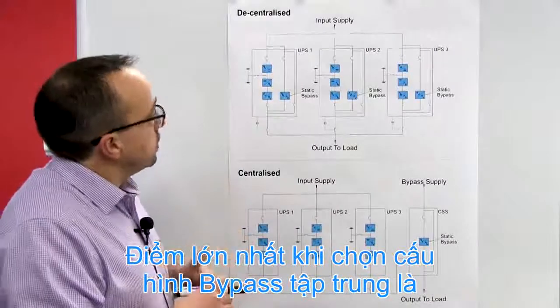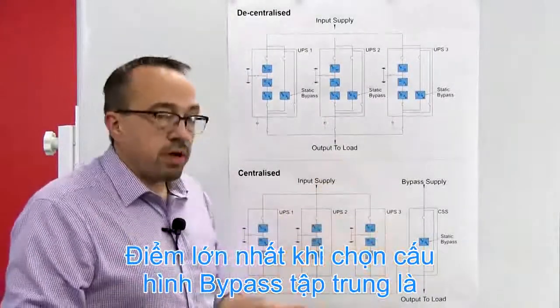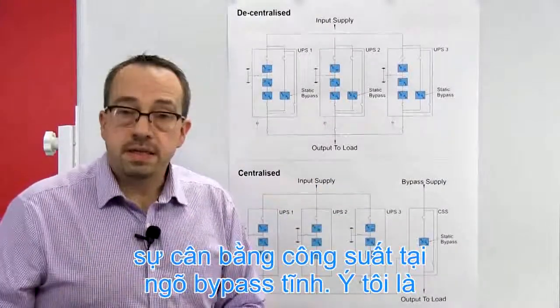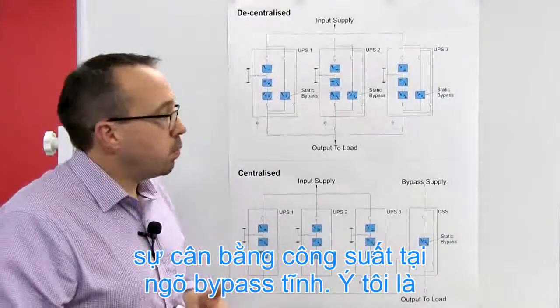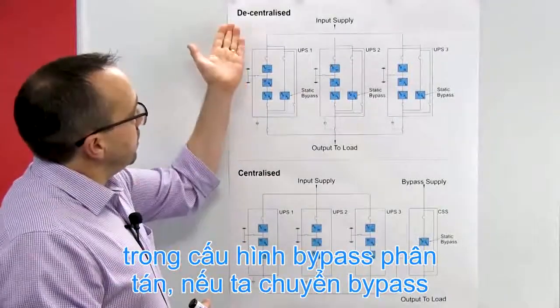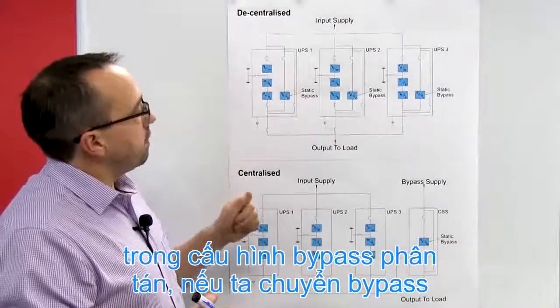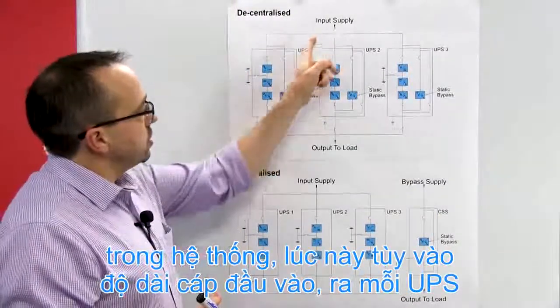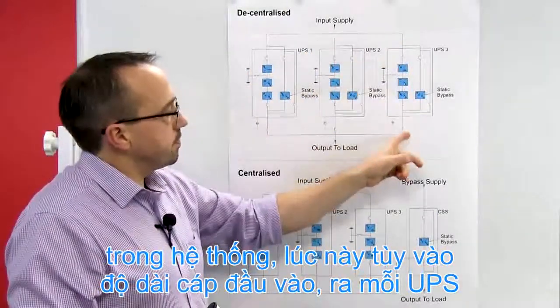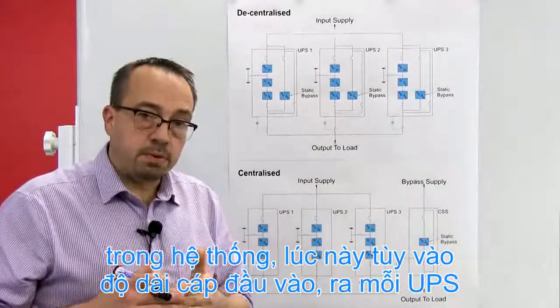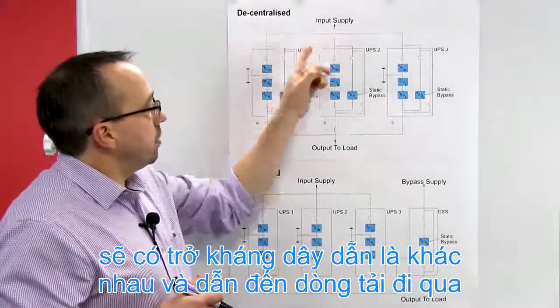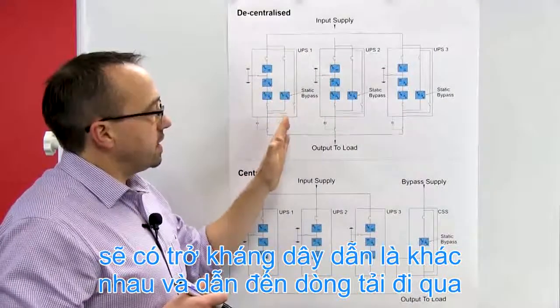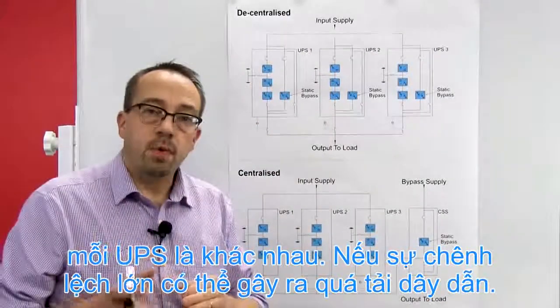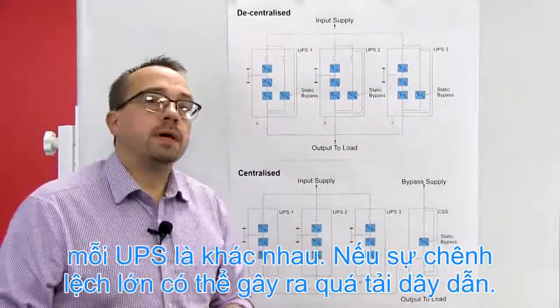Now, one of the biggest points on why people install a centralized system is what's referred to as power balancing whilst on static bypass. Now, what I mean by this is effectively, in a decentralized system, if we go to bypass, we effectively bypass each of the 3 UPS systems. Now, depending on the length of the cables that are fitted between the incomer and the load through the UPS system will dictate the current flowing through each of the UPS systems.